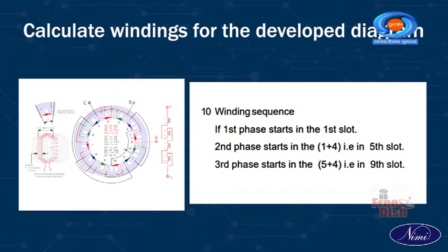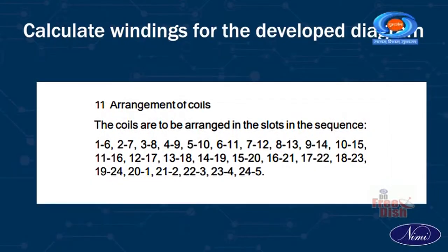9. Winding sequence. If first phase starts in the first slot, second phase starts in the 1 plus 4, that is in fifth slot. Third phase starts in the 5 plus 4, that is in ninth slot. 10. Arrangement of coils.